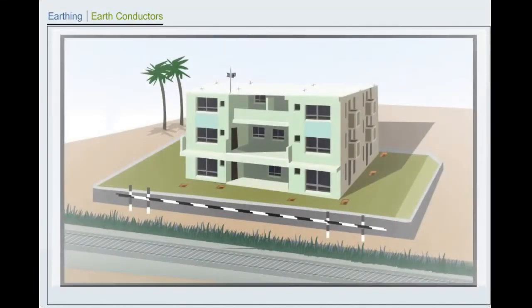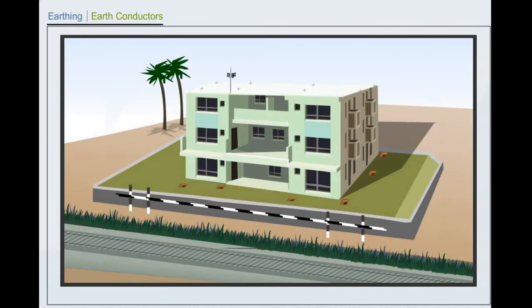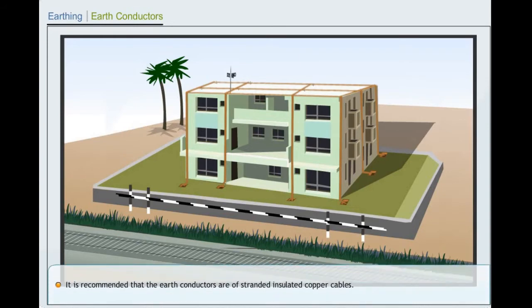Earthing. Earth conductors are typically those conductors that carry the surge to the main point of injection into the ground for equipotential bonding or fault protection and for lightning protection. Earth conductors come out of a building and are finally terminated in an earth pit. It is recommended that the earth conductors are of stranded insulated copper cables.